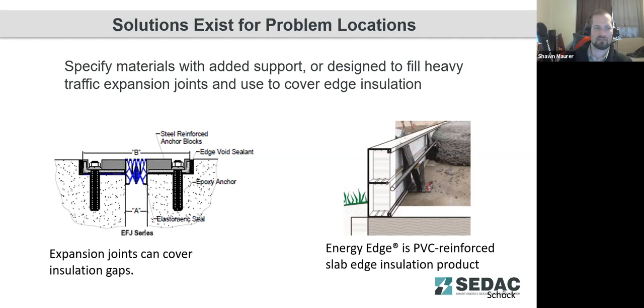But for much heavier traffic, you may want to look into covering that joint with the insulation trimmed down a bit and using a thermally resistant epoxy that provides a little bit of structure. Something we've seen is using expansion joint covers, with the insulation trimmed down enough to fit that expansion joint over top. That provides a little bit of structural support for vehicle traffic so that the insulation itself isn't damaged underneath, and it can maintain the continuity of your thermal barrier around the outside of the slab.